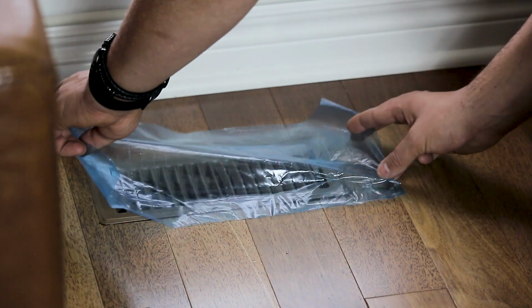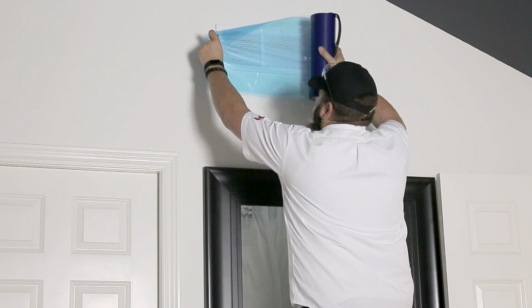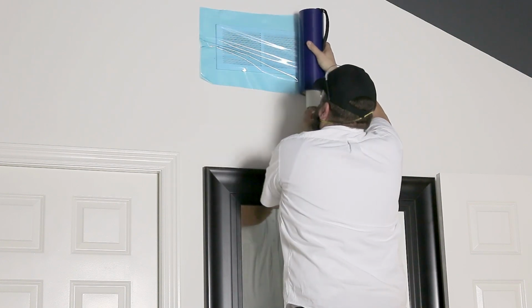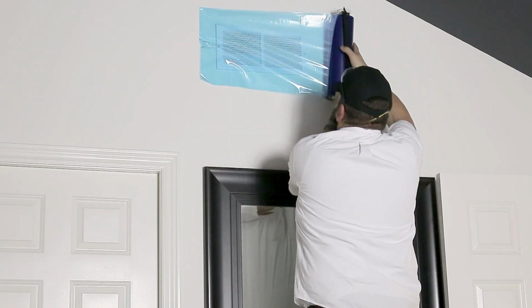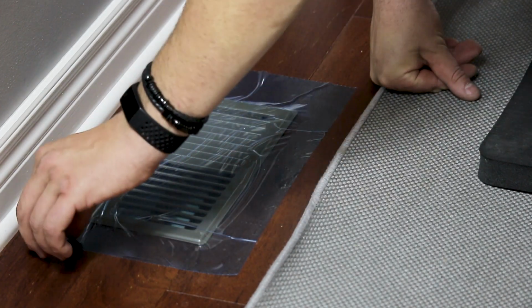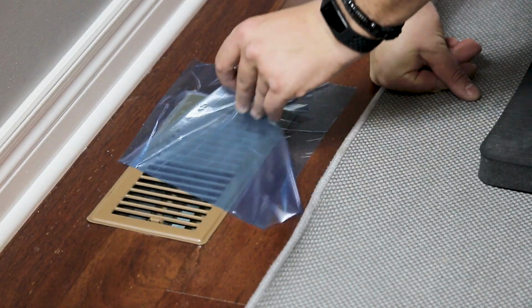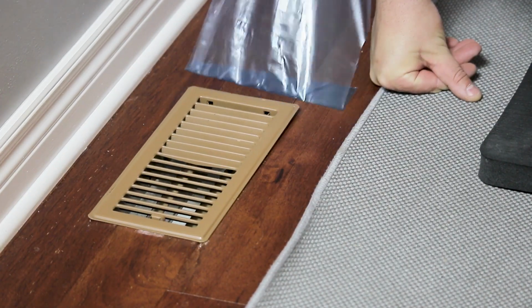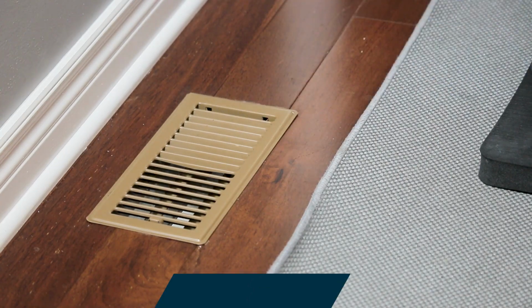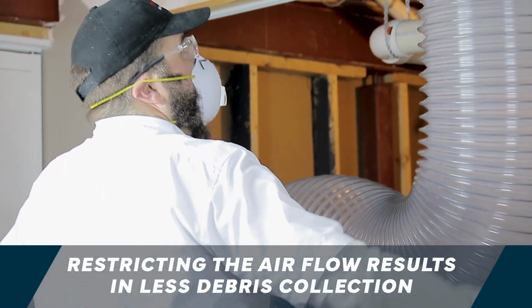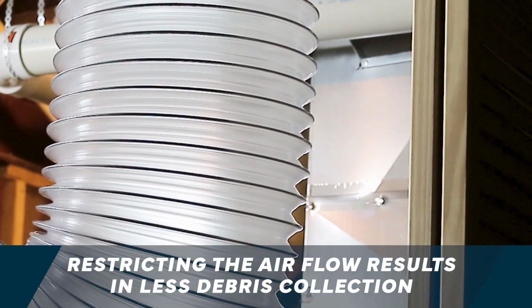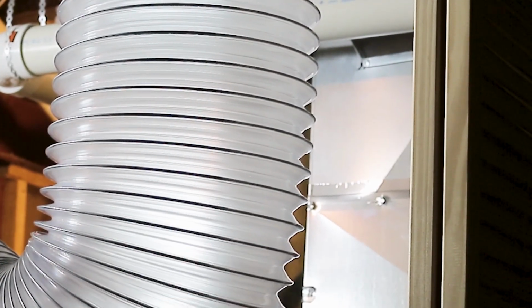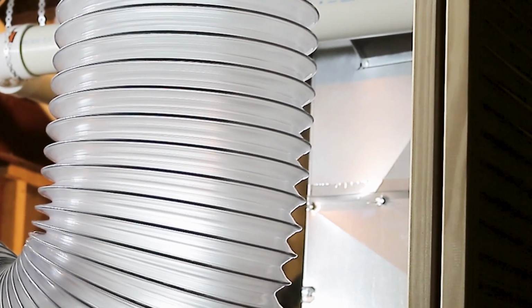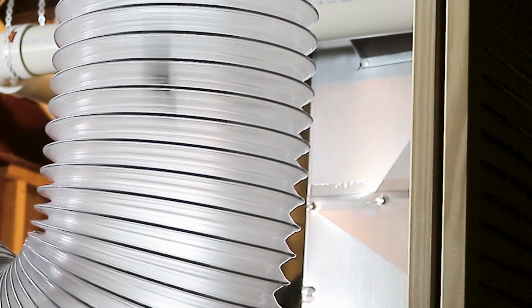Grill mask tape should be put over the registers to seal them off to increase the airflow through the branch run being cleaned. It is important, however, not to cover the furthest 2 or 3 vents in order to allow air into the ductwork to create an airflow. If all the vents were covered, the airflow would be greatly reduced and may be inadequate to transport the debris to the PowerVac. For the same reason, it is imperative that the register of the branch being cleaned is also left open.